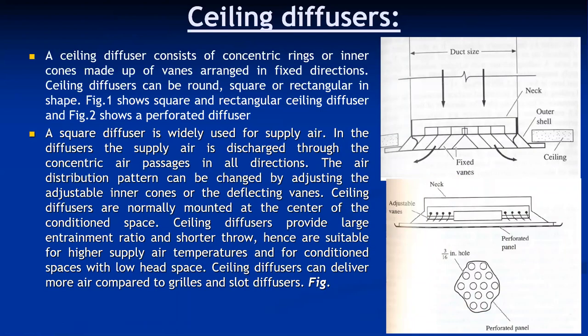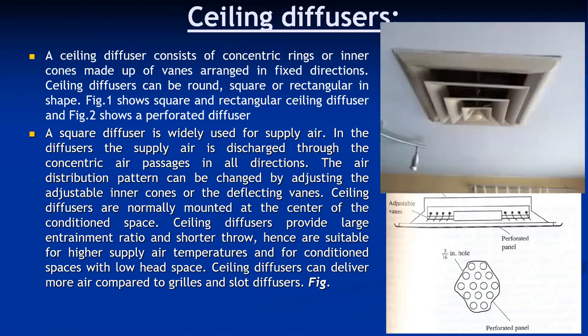Square diffuser is widely used for supply air. In the diffuser, the supply air discharges through the concentric air passages, and the air distribution pattern can be changed by adjusting the adjustable inner cones or deflecting the vanes. Ceiling diffusers have a greater spread and are normally mounted at the center of the conditioned space. They provide a large entrainment ratio and shorter throw, making them suitable for high supply air temperatures in conditioned spaces with low headspace.